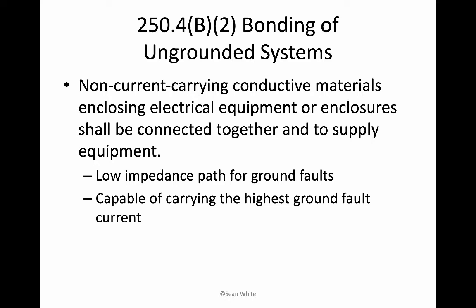We want something to shut off. We want an overcurrent protection device to open up. We don't want some kind of current that takes its time getting through there. We don't want high impedance or high resistance. Also, another thing with our bonding of ungrounded systems is we need them to be capable of carrying the highest ground fault current. And so we're going to look at some of the different tables where we figure out how high the currents are going to be.